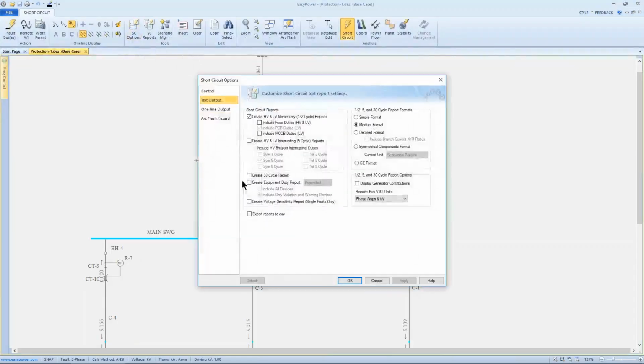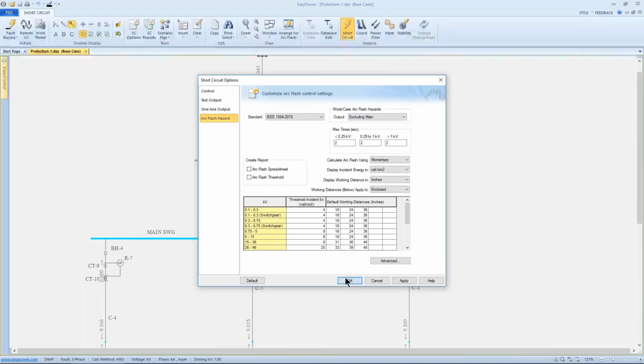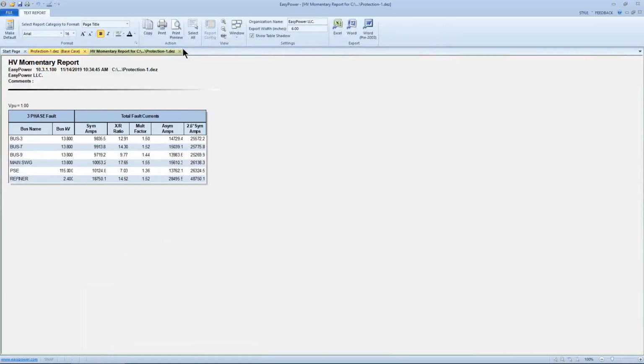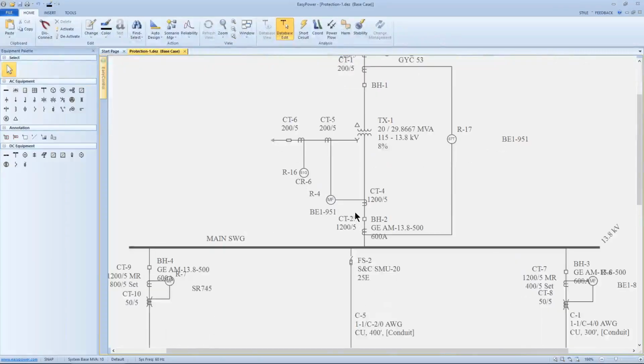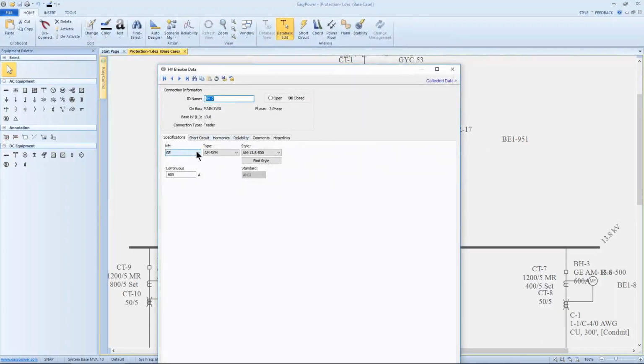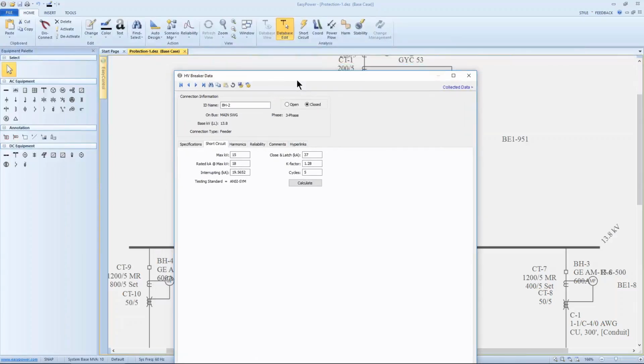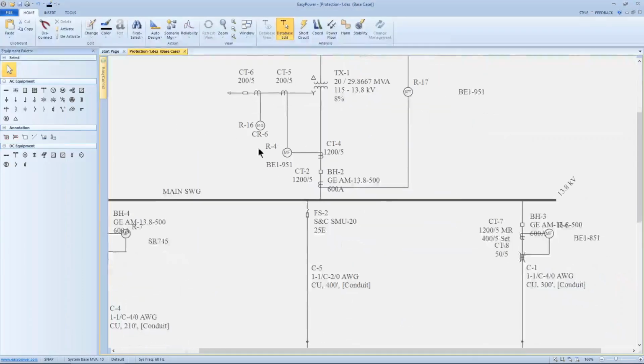I'm going to take off my short circuit spreadsheet. If I go back to the database edit and look at a protective device, say this high voltage breaker, what we see is that the manufacturer, under the short circuit focus, has given us a reference that they are testing to an ANSI symmetrical standard, and these are the ratings listed on the data sheet. These will be pulled up as I make the part selection and then calculate to pull the part number out of the device library. So for every manufacturer's part number that we put together, if you click calculate, it'll pull these numbers up, and these will be used for comparison against the fault current that's being calculated.